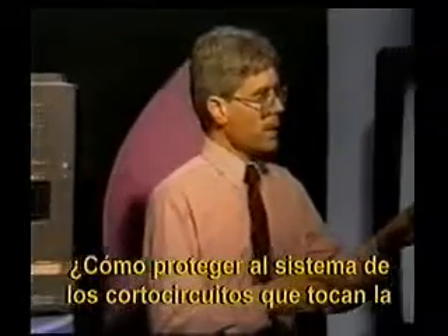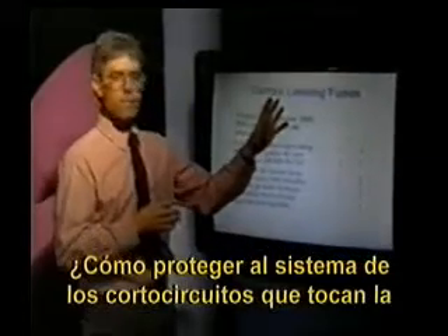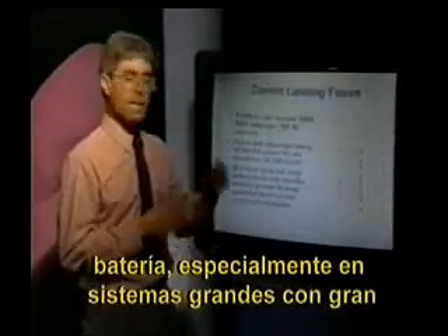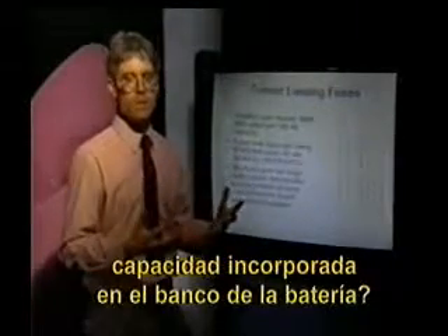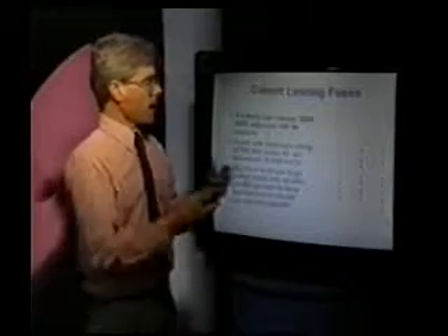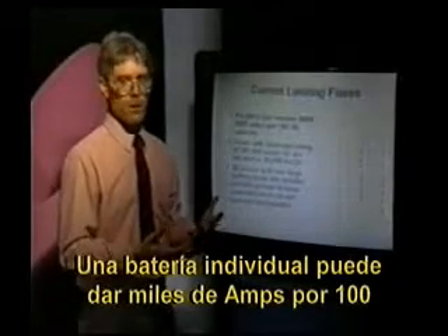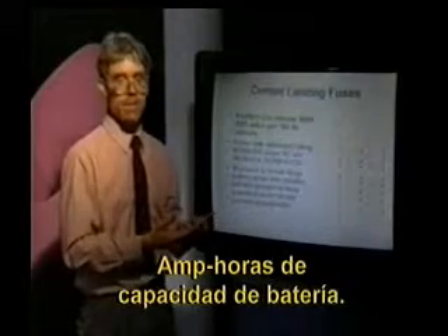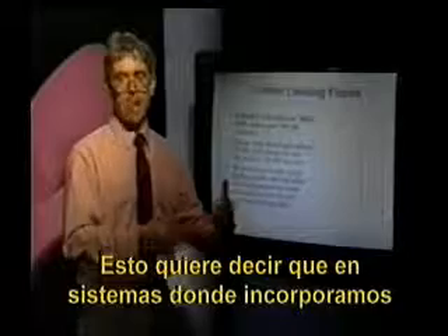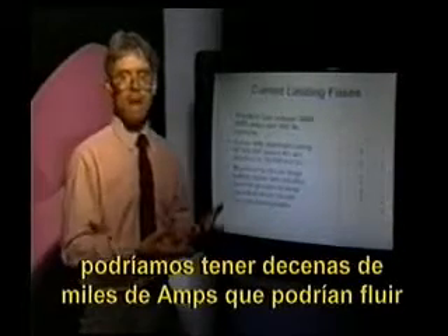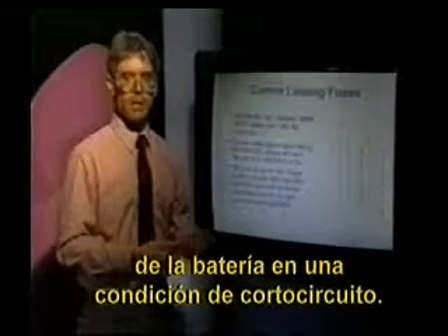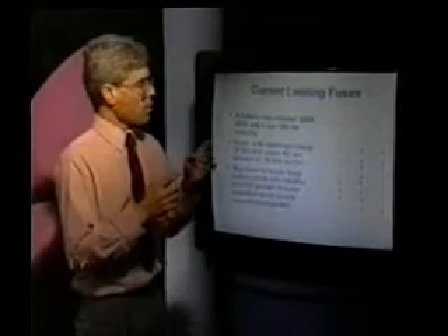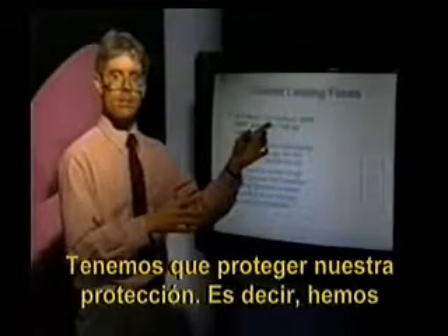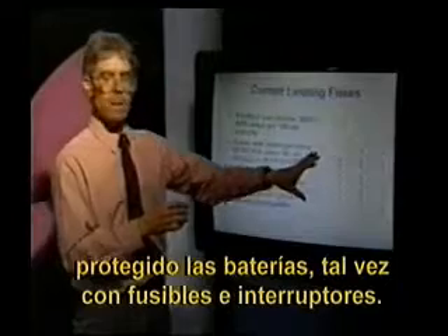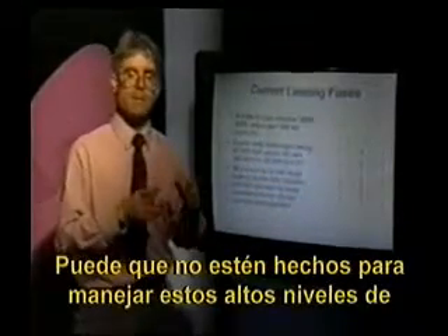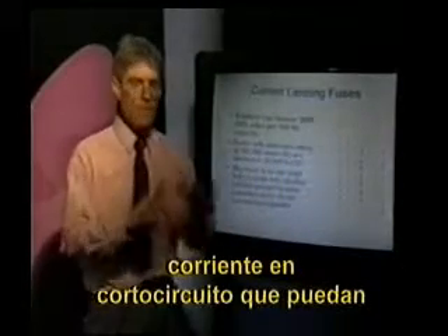One of the concerns that we can look at is how do we protect our system from short circuits touching right back to our batteries, especially in the case where we have large systems with large amounts of capacity built into our battery bank. An individual battery can deliver thousands of amps per 100 amp hours of battery capacity. This means in systems where we've designed in 1,000 amp hours or more of storage capacity, we could have tens of thousands of amps that could flow from a battery under a short circuit condition. We have to be concerned about protecting our protection. In other words, we have downline from our batteries, perhaps other fuses and circuit breakers. These might not be designed to handle these high levels of short circuit current that might occur under extreme conditions.